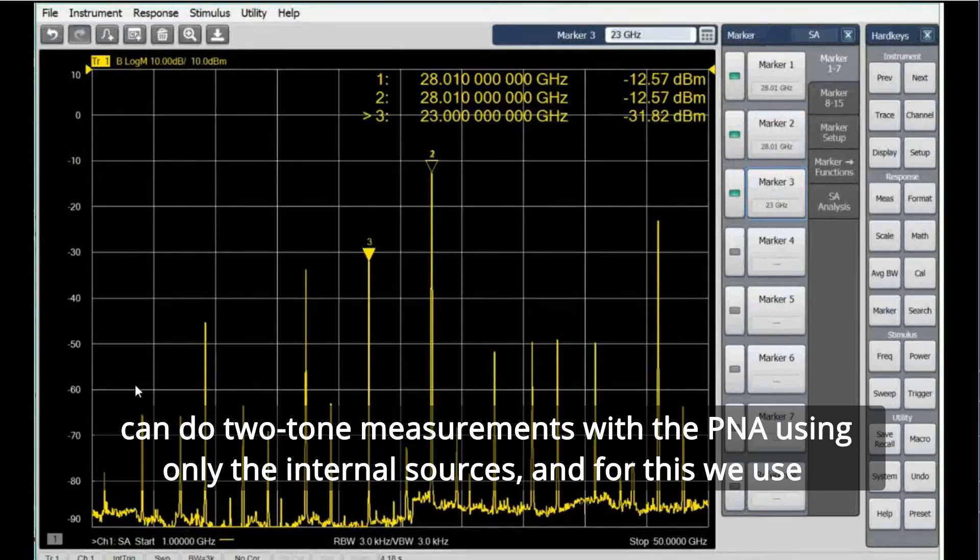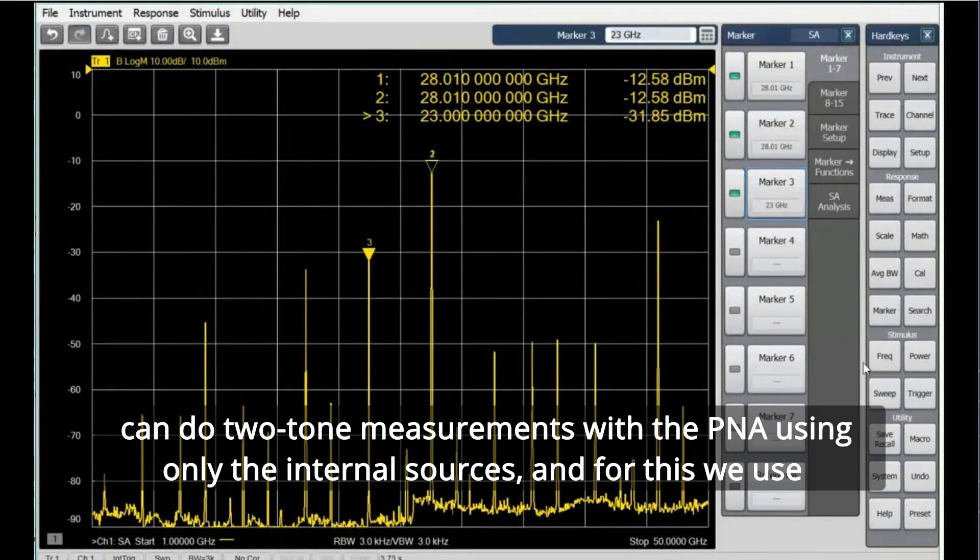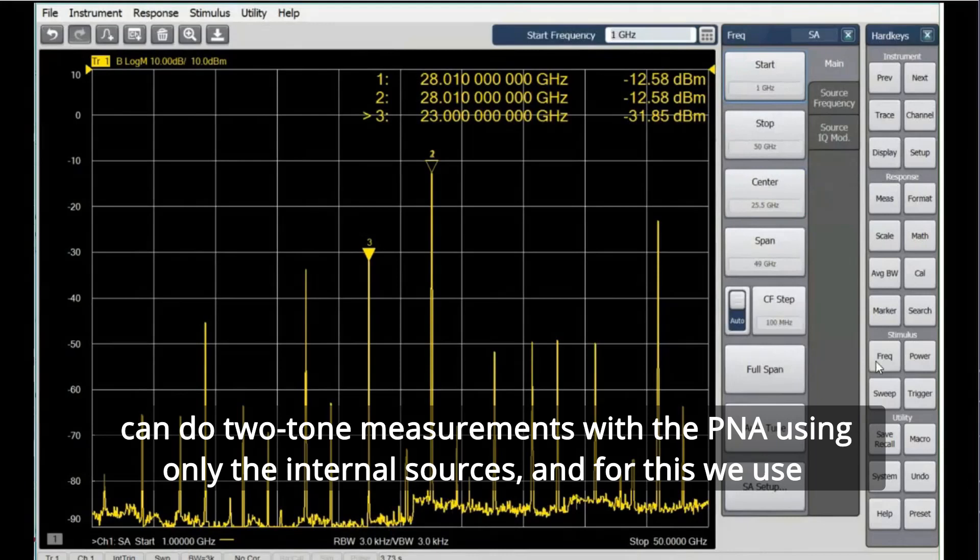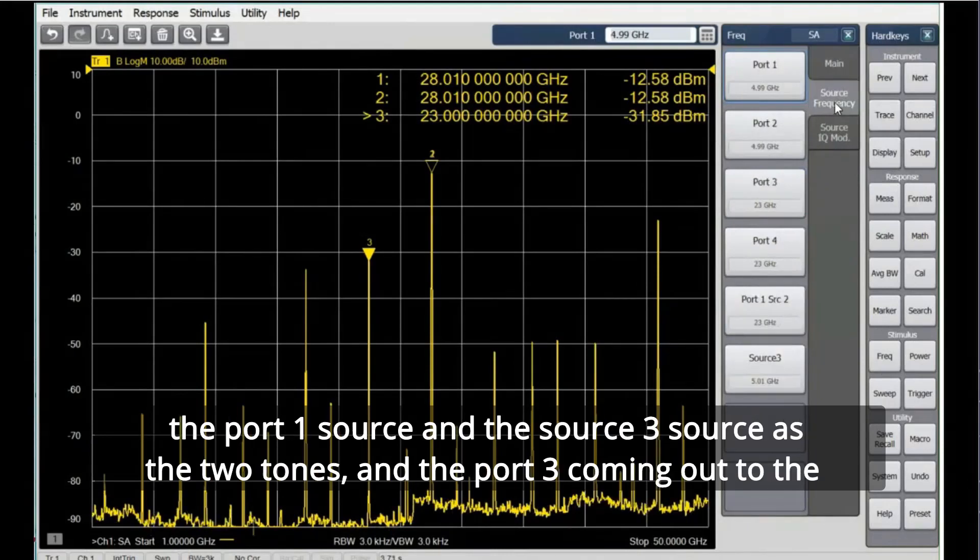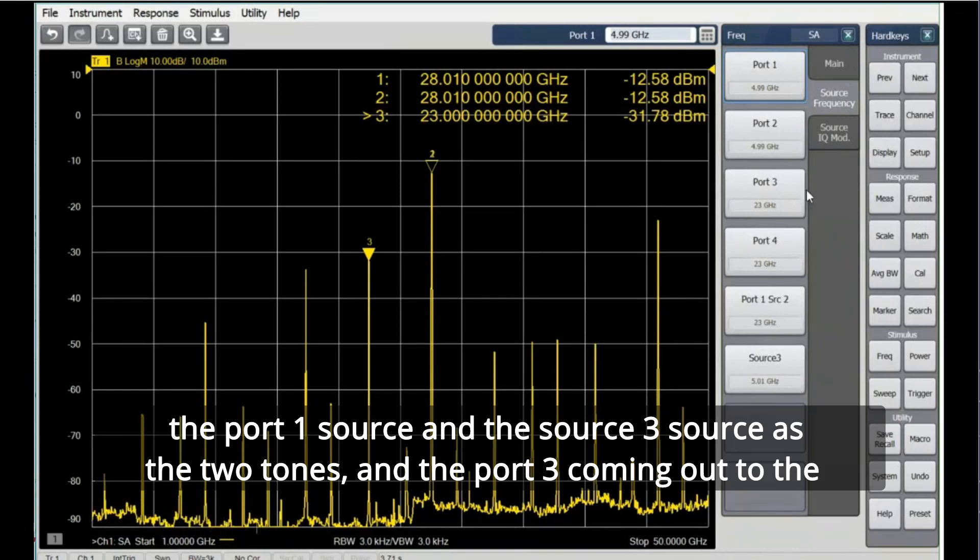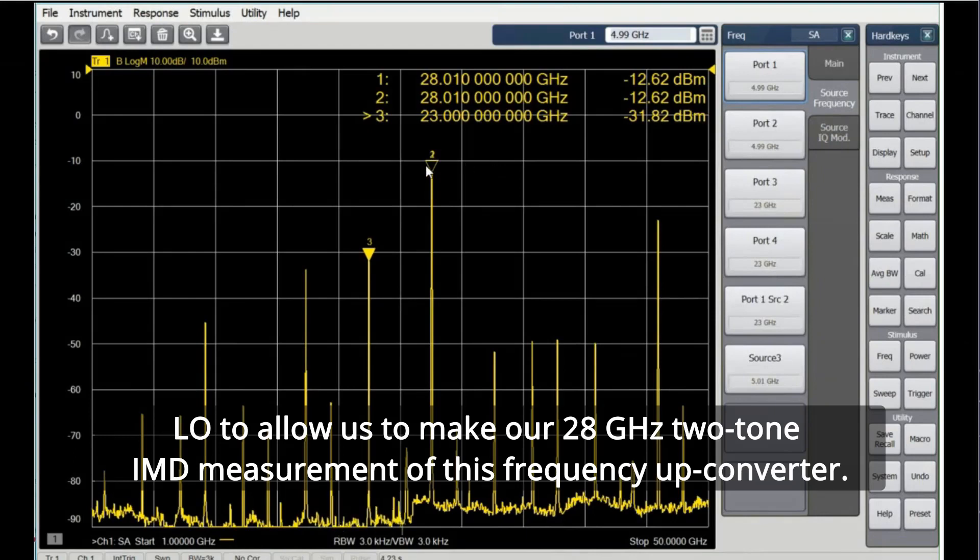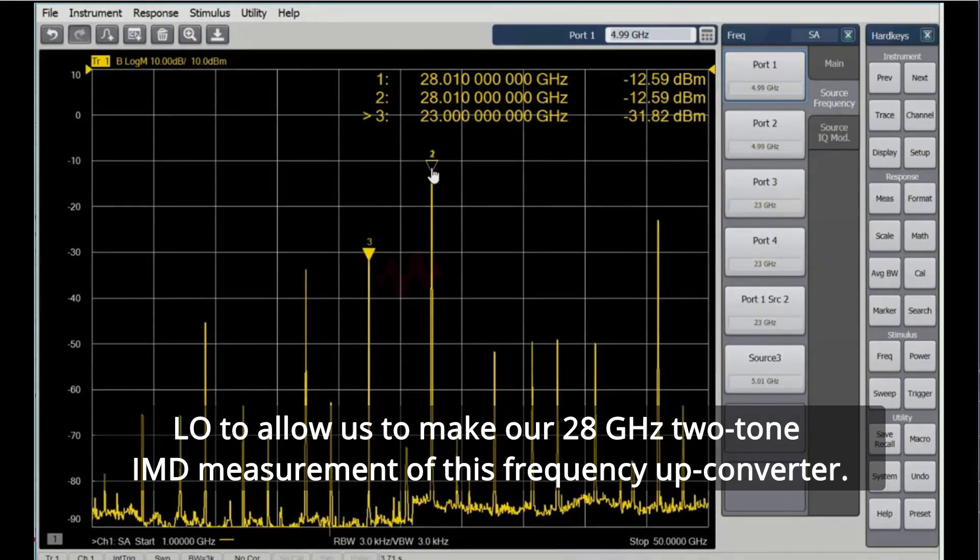So this demonstrates that we can do two-tone measurements with the PNA using only the internal sources. And for this, we use the port 1 source and the source 3 source as the two tones, and the port 3 coming out to the LO to allow us to make our 28 gigahertz two-tone IMD measurement of this frequency upconverter.